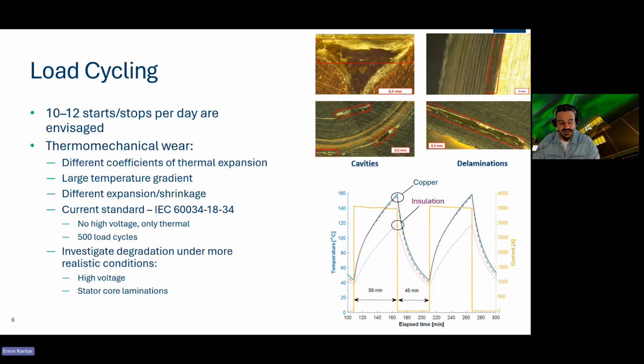And there are some standards proposing guidelines on this thermal load cycling, and the current one is this IEC standard that is mentioned here. In there, it's only thermal load cycling. There is no high voltage applied, and it advises up to 500 load cycles. If there is no change happening, then of course it advises more load cycles, meaning more starts and stops.